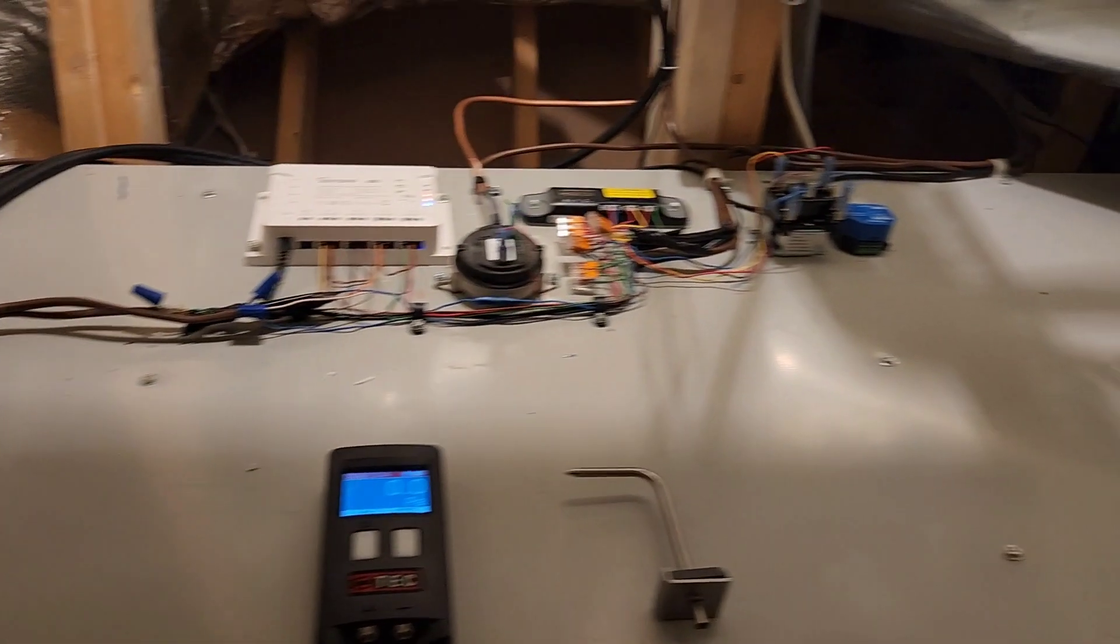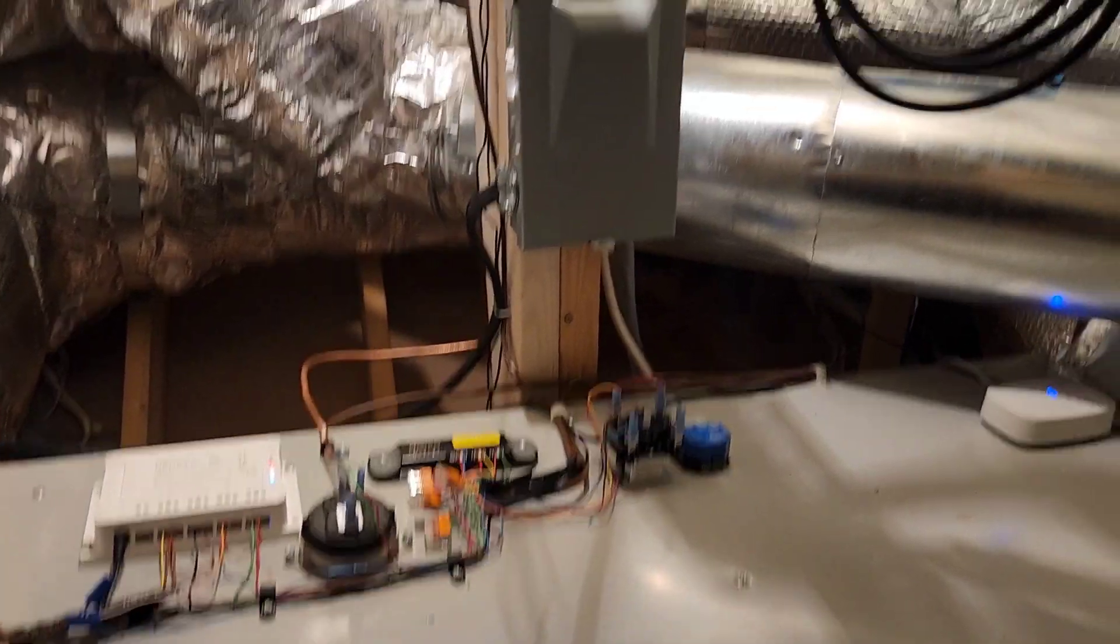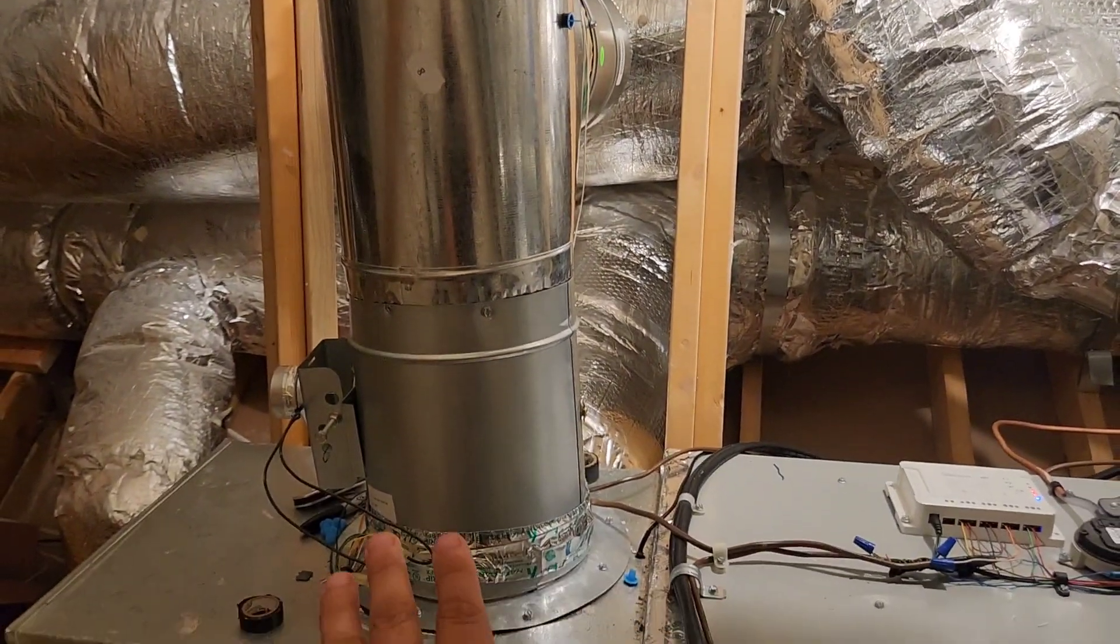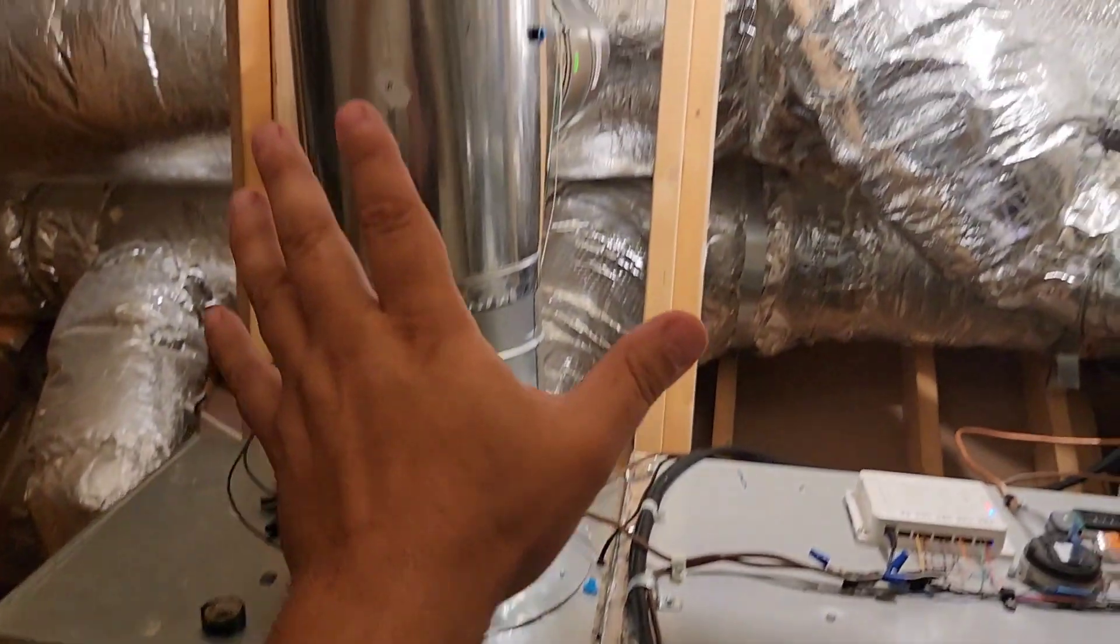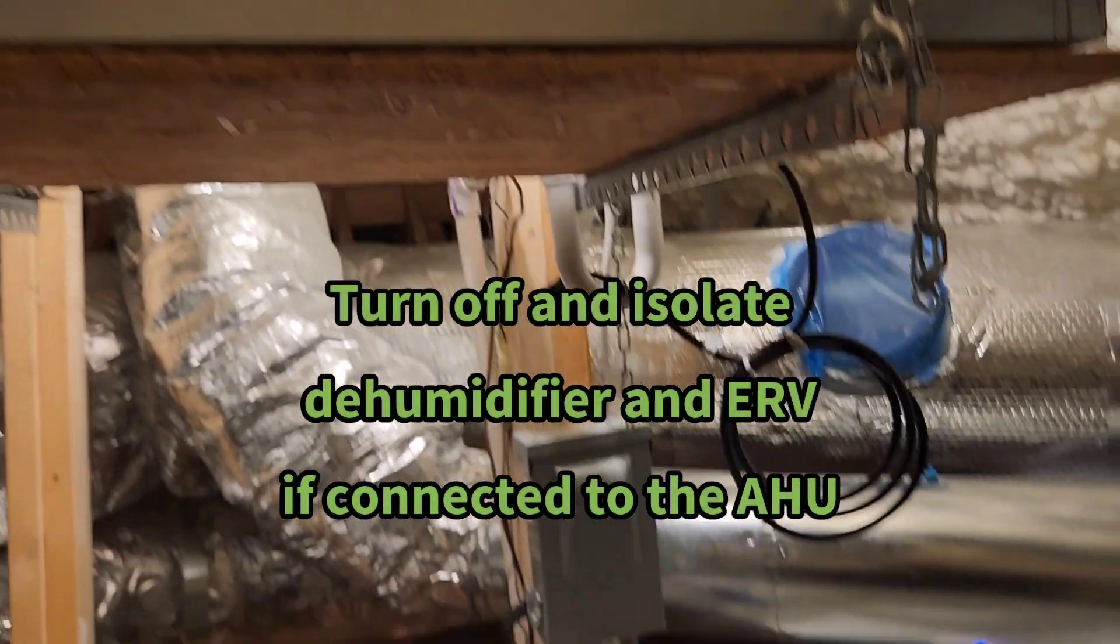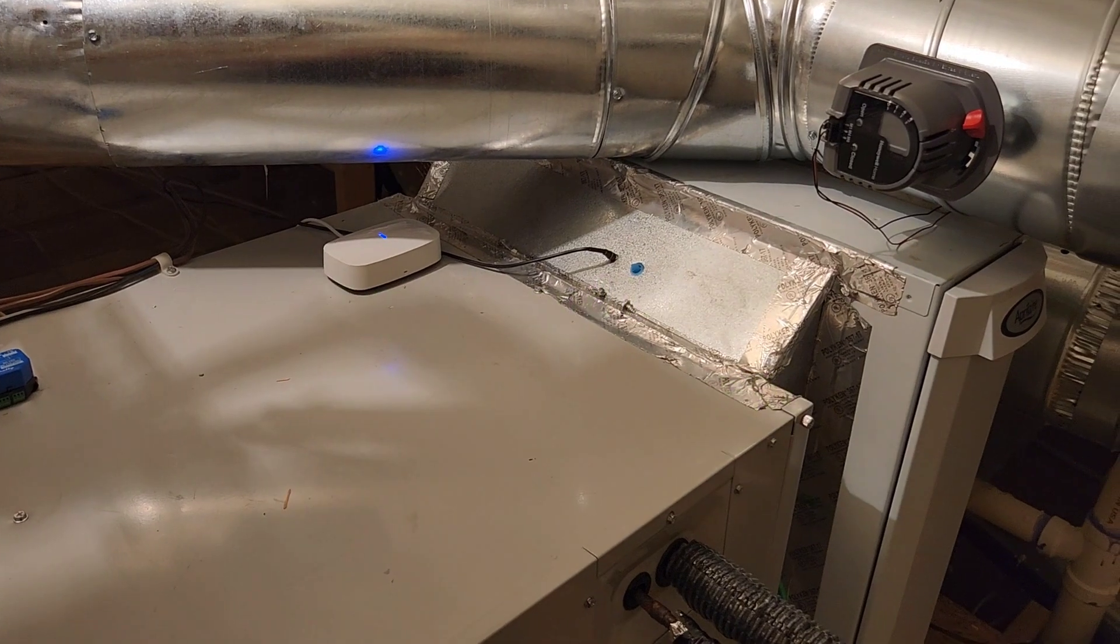Now, this is my home system. I use this as sort of my little playground, my test lab. So I've got a bunch of stuff here I don't want you to pay attention to. Now, with that said, we do need to talk about other air handlers that are tied into the same duct system, because these air handlers can affect the duct pressure as well. If you think we've got an air handler blowing into the supply plenum, and we want to measure the static pressure there, but we got this small air handler also putting pressure in there, that's going to throw things off. The factory did not have a dehumidifier blowing into the supply duct when they quantified that static pressure and turned it into CFMs.